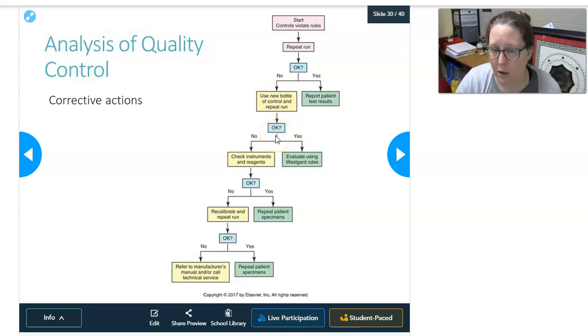If that didn't work, then you have essentially ruled out a problem with the control material itself, and now it's indicating that the problem is in the analyzer. So it could be an instrument problem, it could be that it needs maintenance, or it could be that your reagents are going bad, deteriorating. It could be a reagent issue for that test. Okay, so then you have to check on all of that. Maybe you do some cleaning, maybe some maintenance, maybe you see that your reagent on that assay is at the end of its life, it's almost empty or whatever, and maybe you swap out to a new one of the same lot number, load some fresh reagent on there.